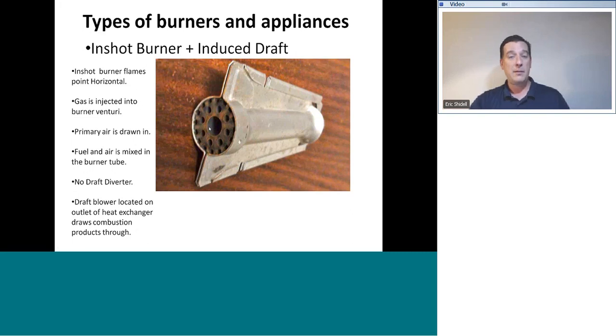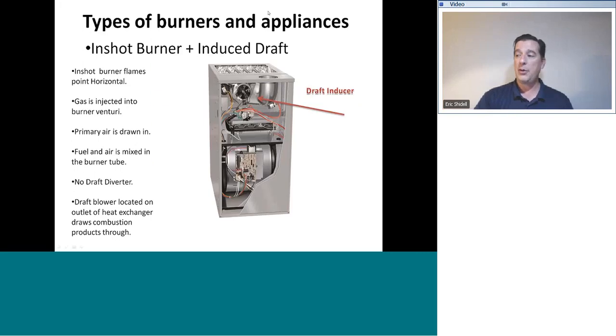A couple of things to be concerned with on burners like this are dust and dirt in these corners, and that these crossovers are clear of debris and not squashed or smashed, because there will be a small ribbon of flame along the rings here on the sides, and that's what's going to ignite the adjacent burner.